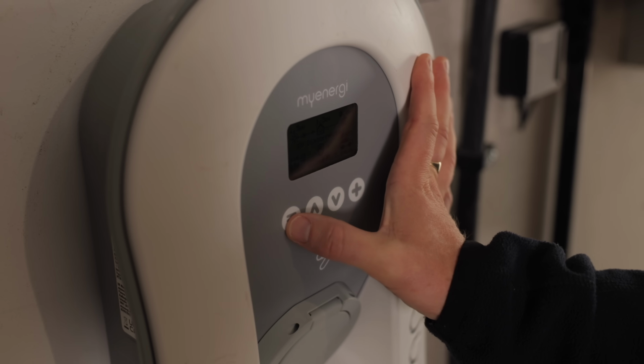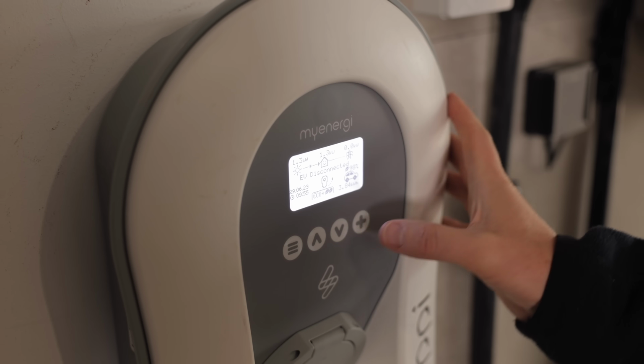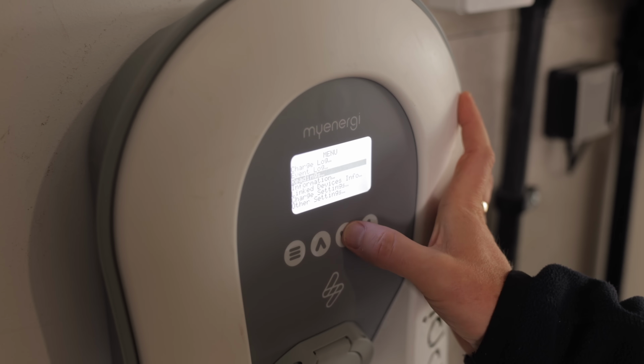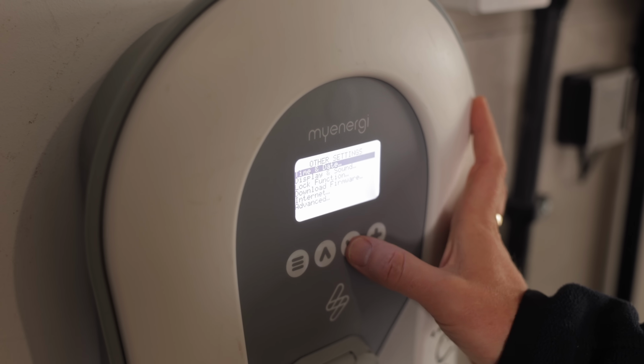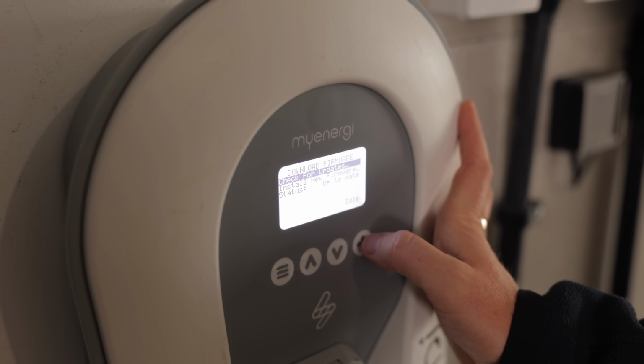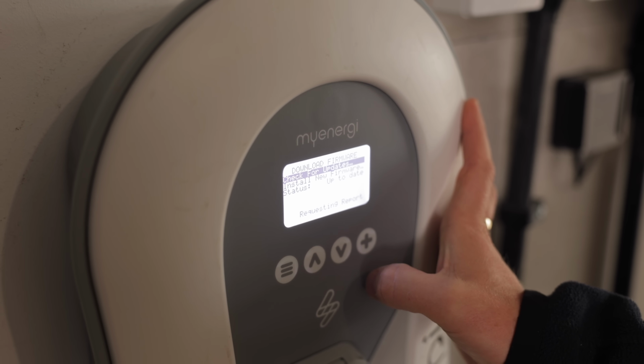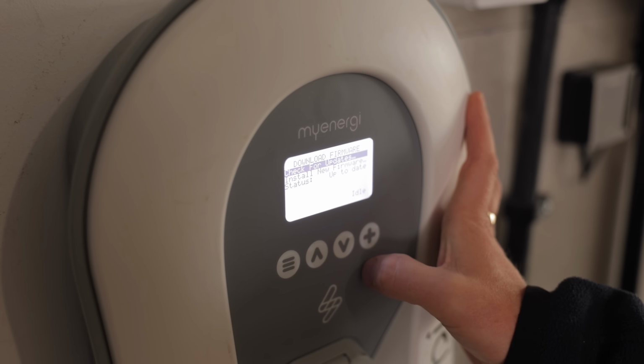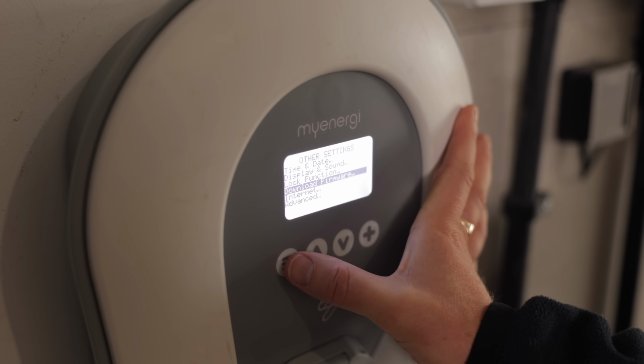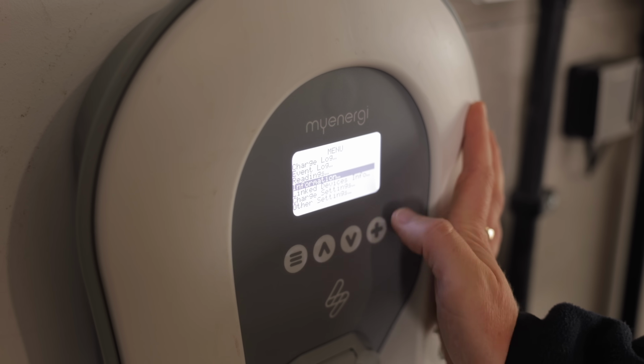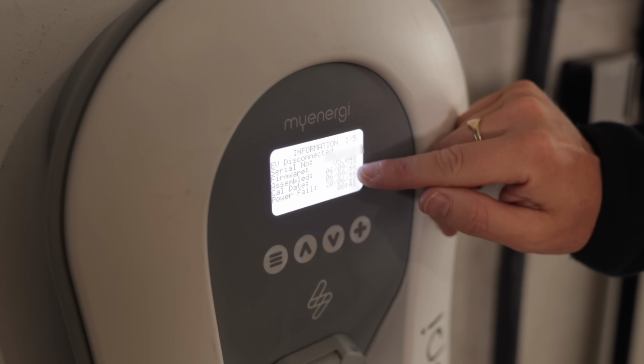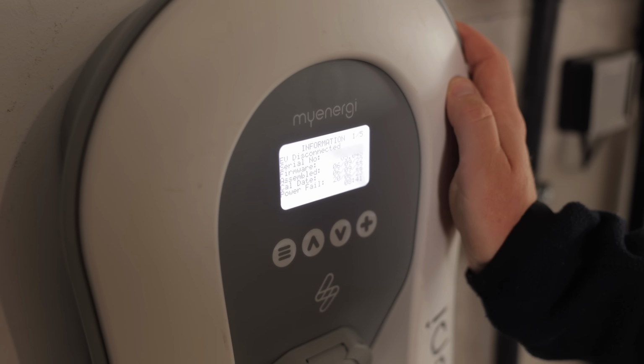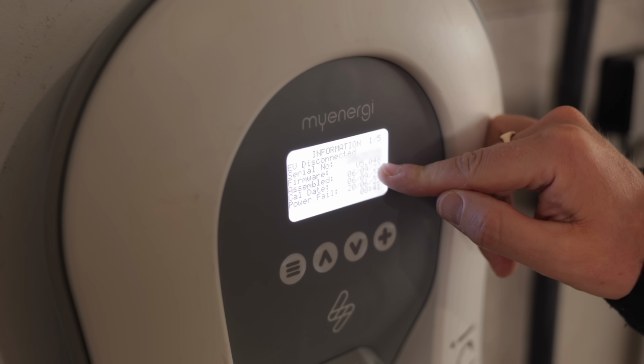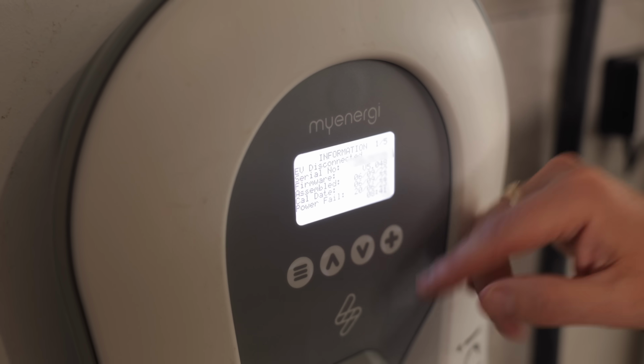So one of the first things I do when I get to site is update the firmware on the existing MyEnergi devices. To do that, you go to the menu, you go to other settings, download firmware, check for updates, and it will request to see if there are any updates available. It says idle and it says status up to date. So if I go to the information menu, I can see what version of firmware. So the customer has already updated the firmware to version 5.048, which is great. That's important because version 5 is the version that they've released since they released the Libbi. If you have version 4 or earlier, the other devices won't know what a Libbi is, and then they won't be able to talk to it.